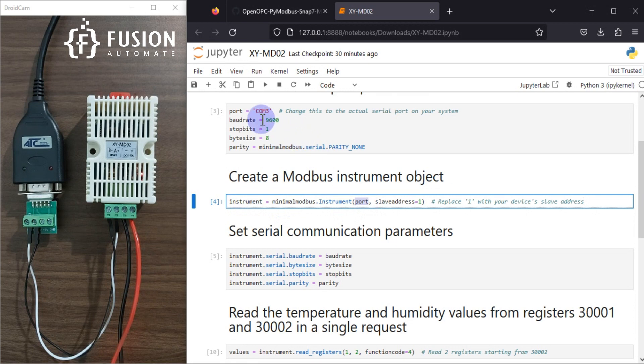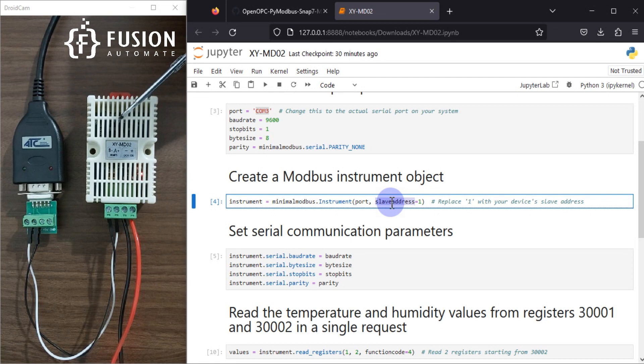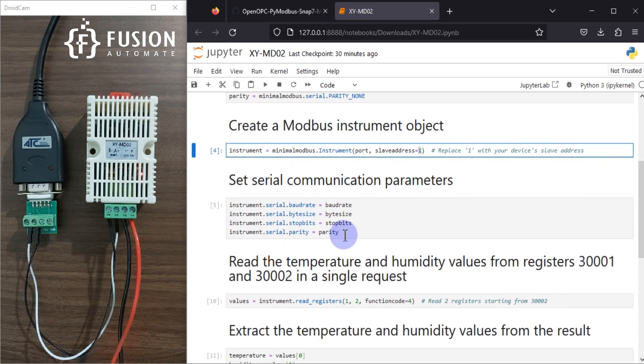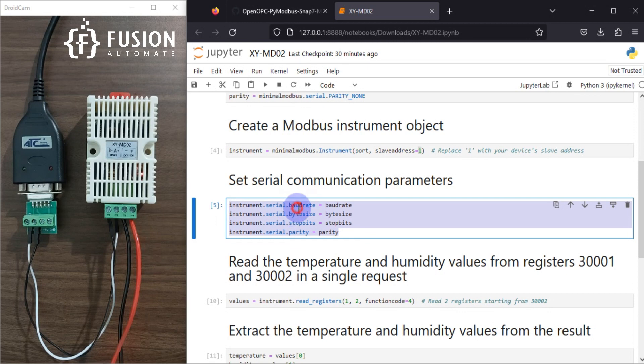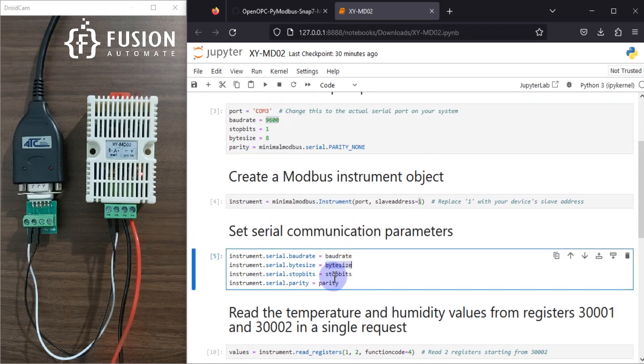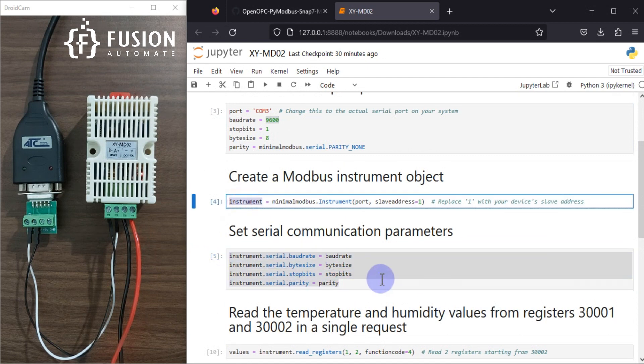The port number is COM3 and the slave address — this device has a slave address or device ID of 1. If you have another device with a different slave ID, you can specify that here. After that we set the parameters on the instrument object: baud rate 9600, byte size 8, stop bit 1, and parity None — everything is added into the instrument object.